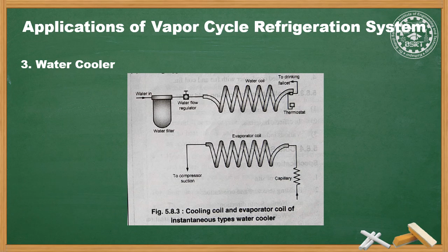Equipment used are a hermetically sealed compressor depending upon the capacity of the cooler, capillary tube, flooded type evaporator, and air cooled condenser with fan and coil. Applications are, we know, that it is used in colleges, hospitals, offices, various industries, etc.